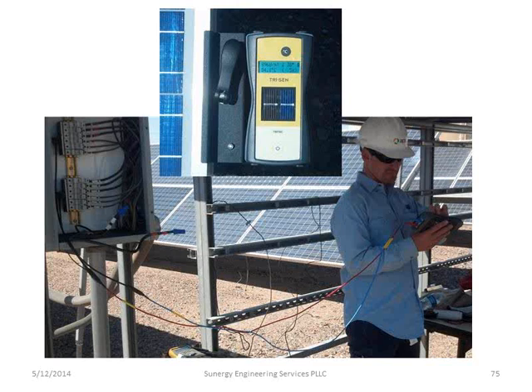But it is small and compact, and you can see here they're doing it. These are old 300-watt modules that were originally in what I think was called the Star Center—they did a lot of PV testing in Arizona early on. Those modules look really bad, with corrosion and delamination, and they're only about 15 years old. We actually had problems megging them because they were all so bad, it was really hard to get a comparison.